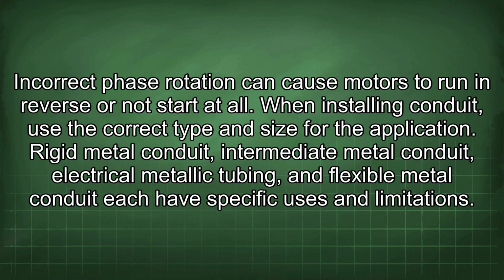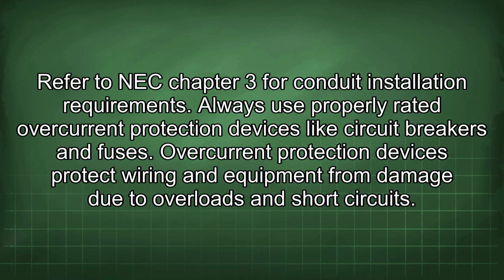When installing conduit, use the correct type and size for the application. Rigid metal conduit, intermediate metal conduit, electrical metallic tubing, and flexible metal conduit each have specific uses and limitations. Refer to NEC Chapter 3 for conduit installation requirements. Always use properly rated overcurrent protection devices like circuit breakers and fuses. Overcurrent protection devices protect wiring and equipment from damage due to overloads and short circuits.